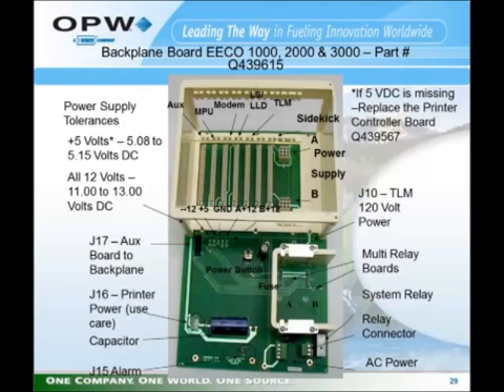If the main power supply loses 5 volts completely, you need to check to make sure that has not happened, that someone has not plugged that connector in wrong. If they have, when you install a new power supply and turn the power on, you will blow the new power supply. So if you are not sure if that condition has occurred, when you replace the power supply, you will also want to replace the printer controller board.